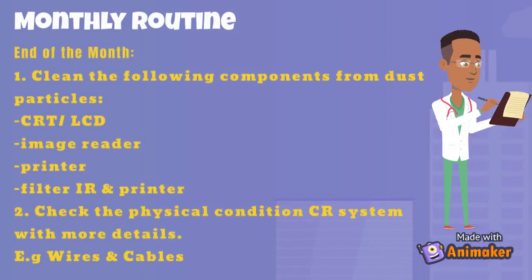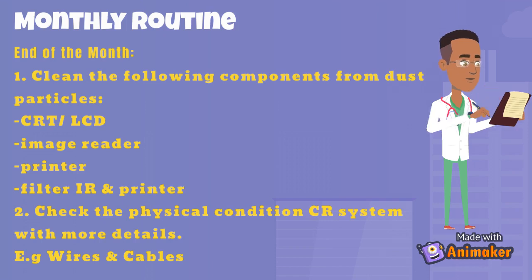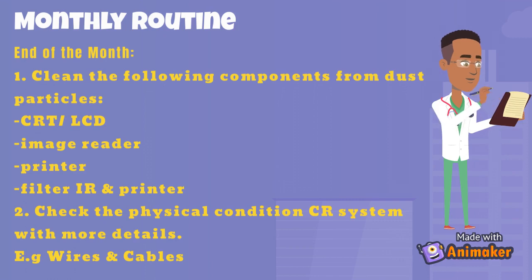Besides daily and weekly routines, the quality assurance for the CR reader can also be done through a monthly routine at the end of the month. This includes cleaning the CRT or LCD from dust particles, cleaning the image reader and printer from dust and debris, clearing the filter of the image reader and printer from dust, and checking the physical condition of the CR system in more detail.